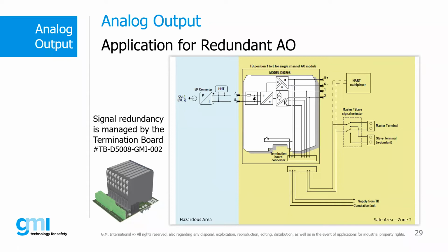Through this switching logic, it's possible to carry out redundancy also for analog output circuits. And there are two different concepts for the use of redundancy: the one that looks at the safety of the process, and the one that looks at the availability of the process. The two philosophies of redundancy are in contrast with each other, and the end user must choose which way to go. GMI's analog output redundancy satisfies the concept of process availability, allowing our plant to continue its work even if one of the components in the field fails.